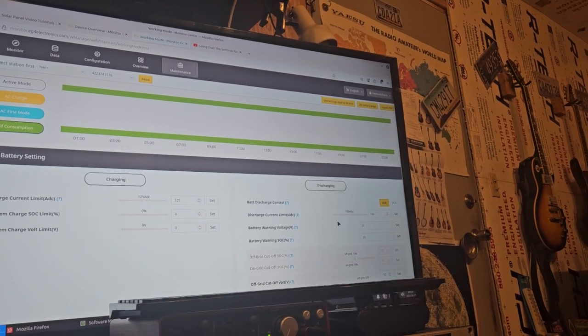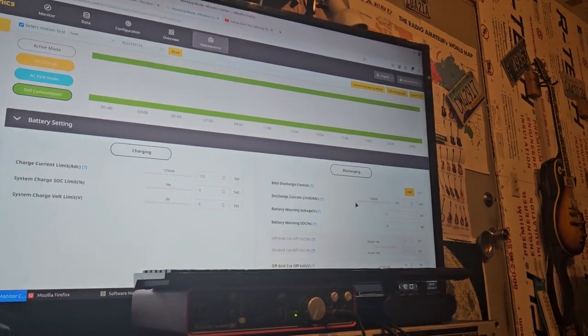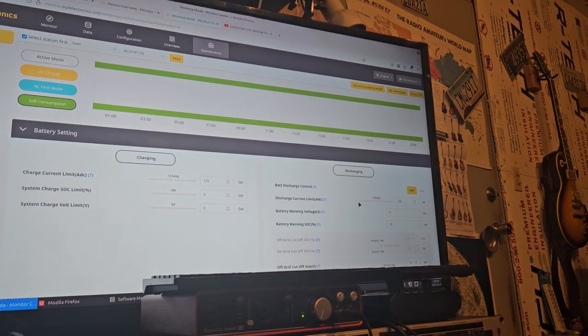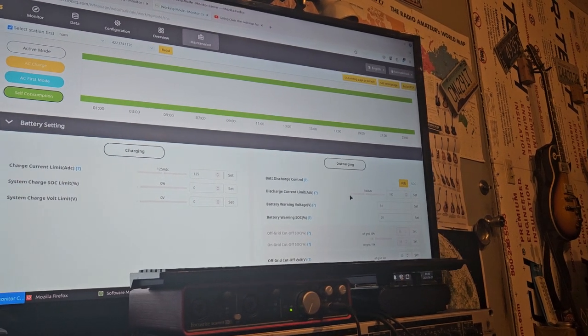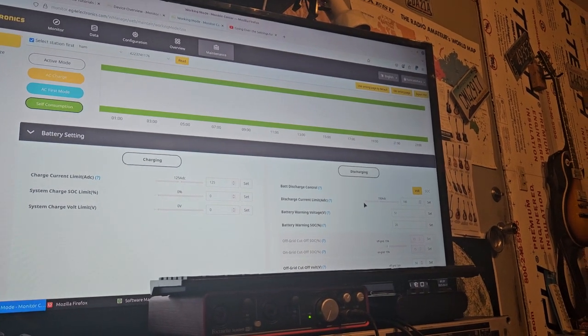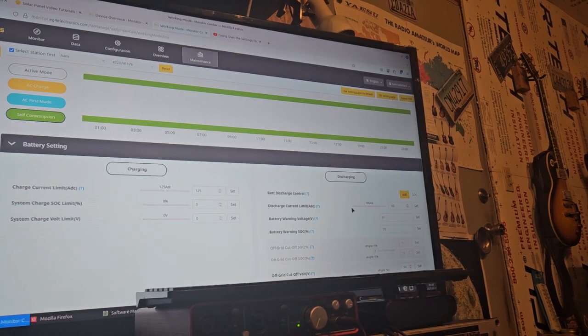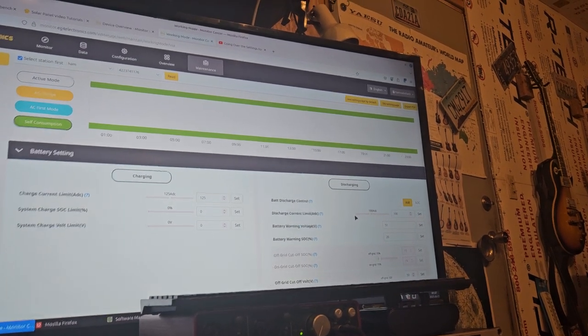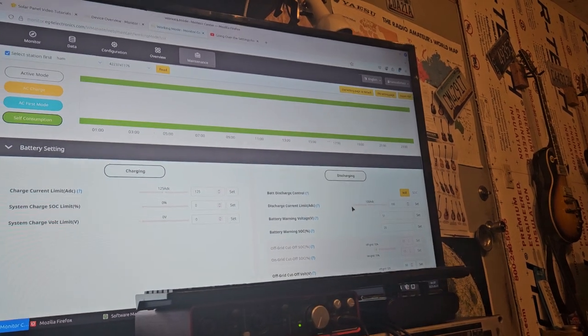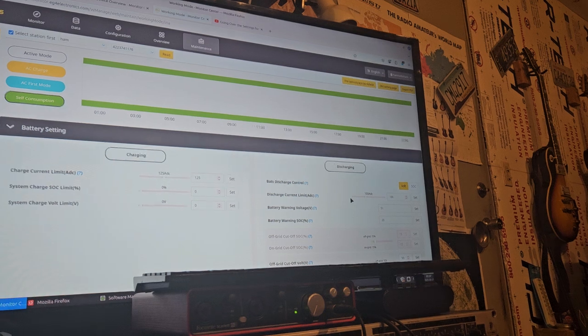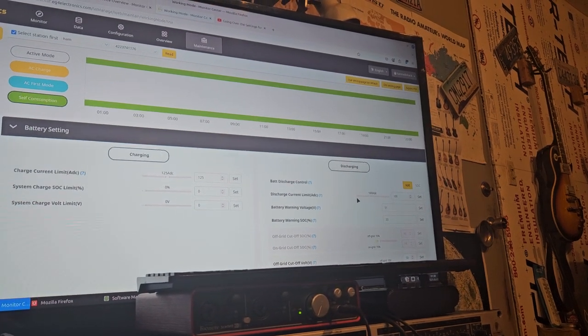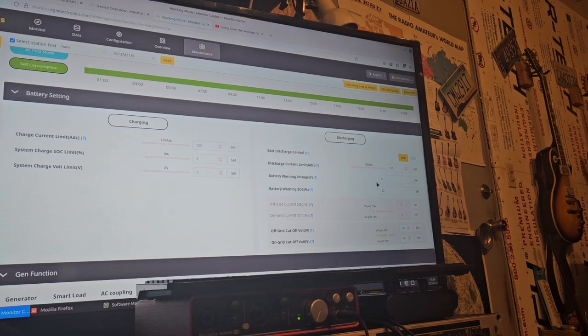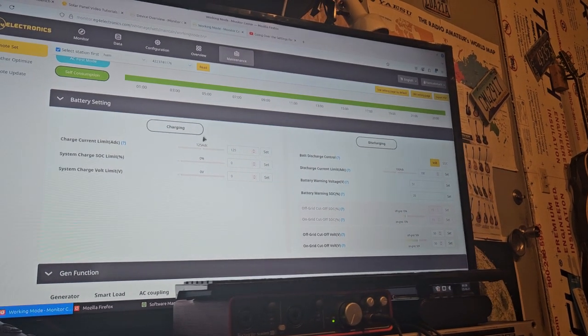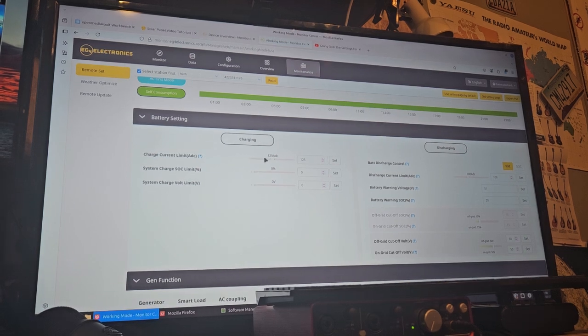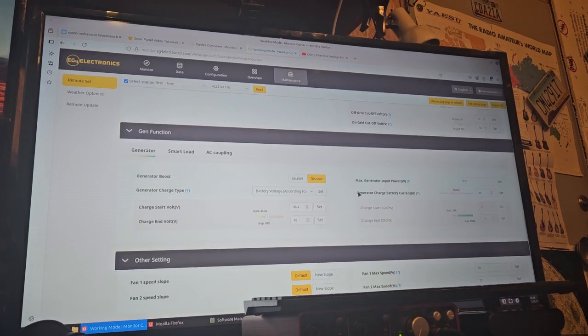And then you have discharging over here. I set it to 100 amps. I don't want it to discharge more than what they're rated at. I mean, 100 amp hours is not necessarily 100 amps output. These batteries can provide way more than 100 amps if you suddenly put a major load on them. There's a cutoff usually on the BMS at 150 on most 100 amp hour batteries. So I want that under that, I don't want to be causing myself problems. I don't really want to dump 125 amps into the battery either, but I have a feeling that's probably not going to happen too often.